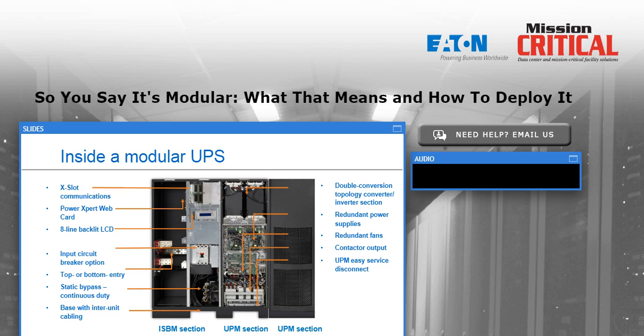And then to the right of that, there are 2 UPM sections, and they are identical, each one capable of 300 kilowatts in this case. And in a system like this in the U.S., if we are going to work on either UPM with field service engineers, the fire code requires that we go ahead and bypass the UPS or put it on the maintenance wrap, the wraparound bypass that's typically deployed with these types of machines. So if I'm going to need to bypass the UPS to perform service, I want that service to be done as quickly and safely as possible. So kind of like we saw in the smaller modular UPS systems, everything is a pull-out assembly. In the top of this UPM, you see on the left there's a drawer that's a pull-out rectifier for the entire UPM. And on the right is the pull-out inverter, which can slide out, slide in, and quickly get the system back up and running. Contactors, filter capacitors, fan banks, and all the circuit boards are mounted on the front of the area there, again, for fast service. It can be accomplished safely.